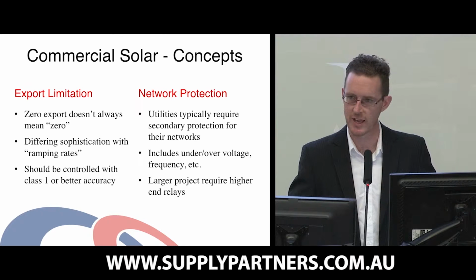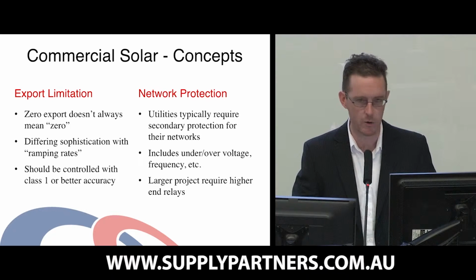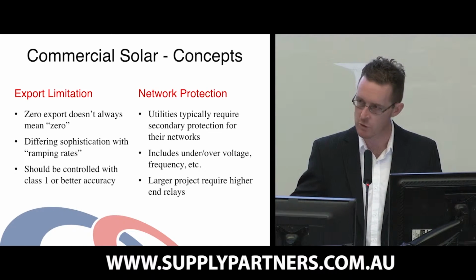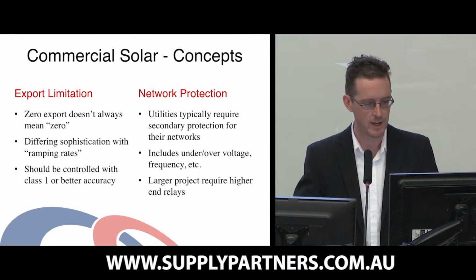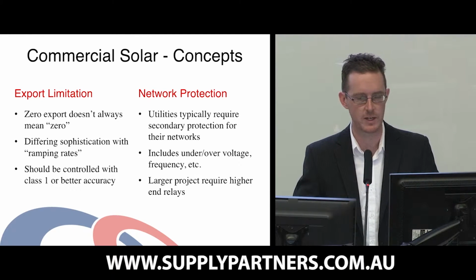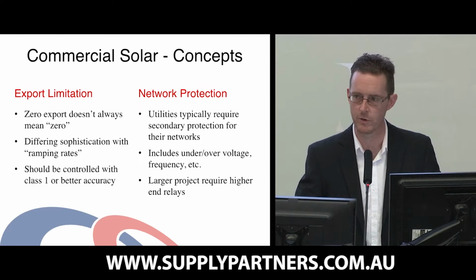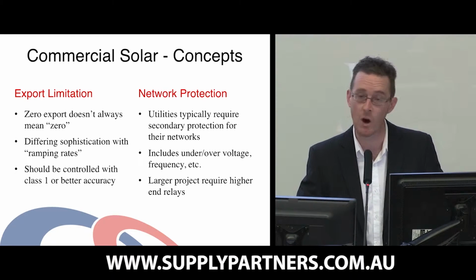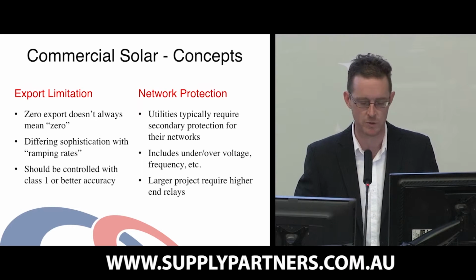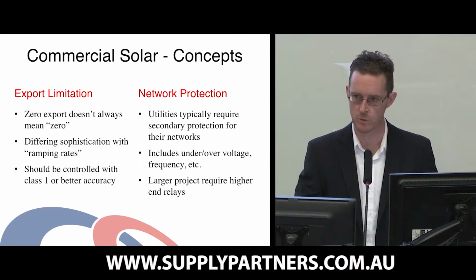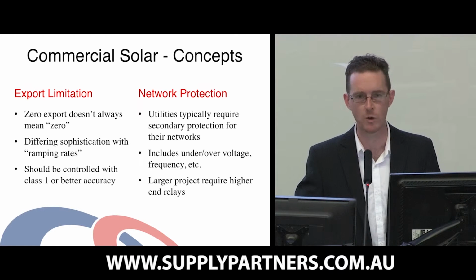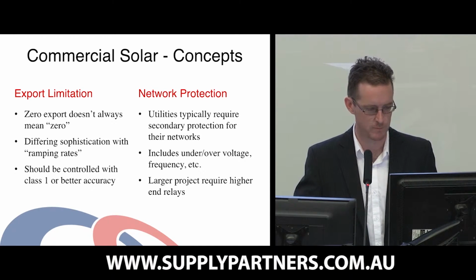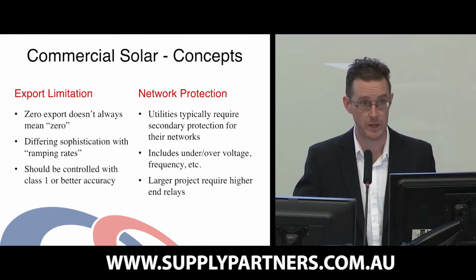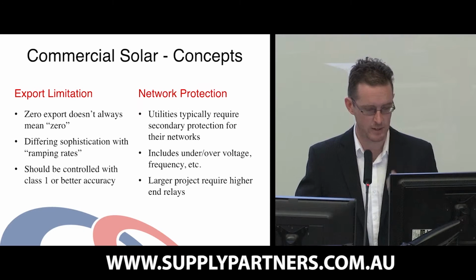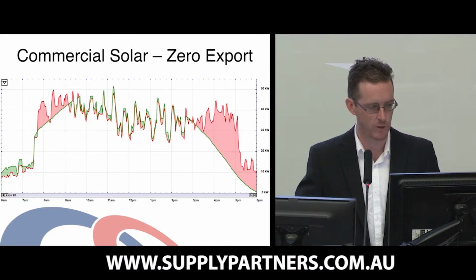Ramping rates, this is just how smoothly we can increase or decrease the inverter's output to match the load. You want the smallest steps and the smoothest operation possible. And then network protection. For systems over 30 kilowatts, utilities say, well, look, we understand that your inverters will turn off if the voltage is too high or too low, or the frequency is out of range, et cetera, but our grid is worth a lot of money to us, and we want to protect it. So we want you to install secondary protection. And when you get into the really big projects, the megawatt style, the requirements around this really ramp up.